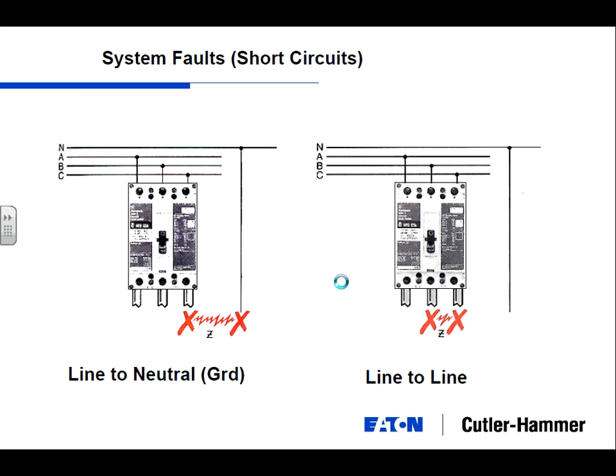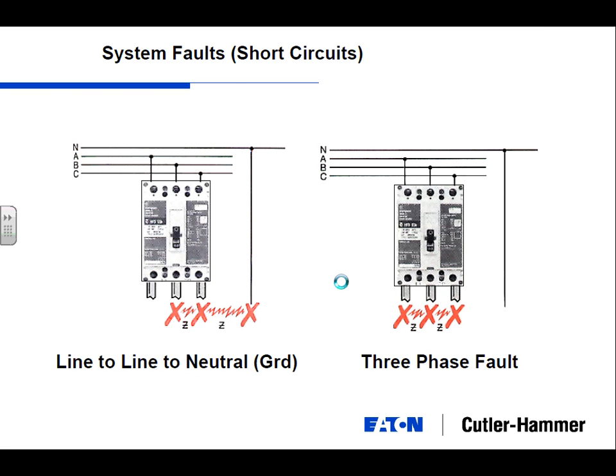So we've got just a couple pictures here on the different types of faults or short circuits available. You've got a line to neutral fault, which is, say, on a 120 volt receptacle. I'm creating a path of low resistance, but still resistance between A phase and neutral. Line to line, between A phase and a B phase is a fault. Line to line to neutral can be a fault. And then the most dangerous out there is the three-phase bolted fault. All three phases are tied together.